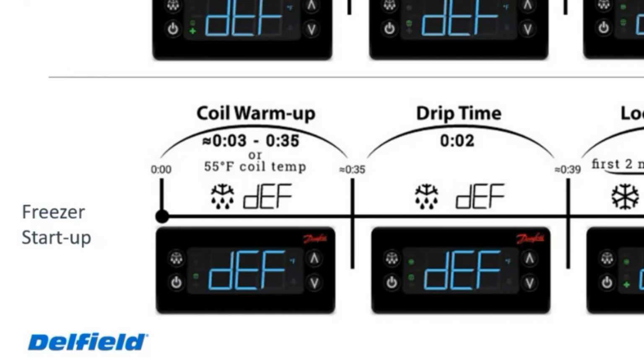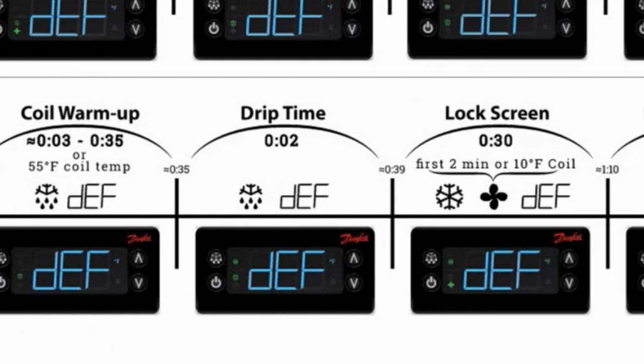After the defrost is completed, we'll go into drip time. Still going to read DEF on the display, still going to have that melting snowflake. That's going to last 2 minutes. So that's essentially an extension of the defrost. The only difference is that the heater won't be energized.